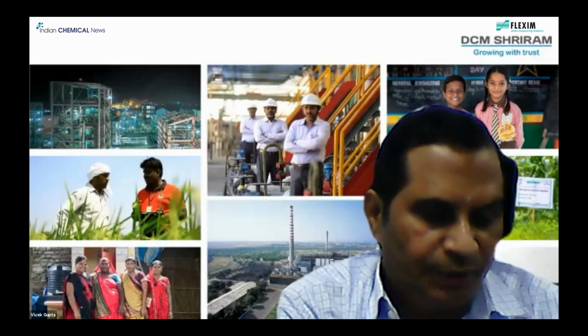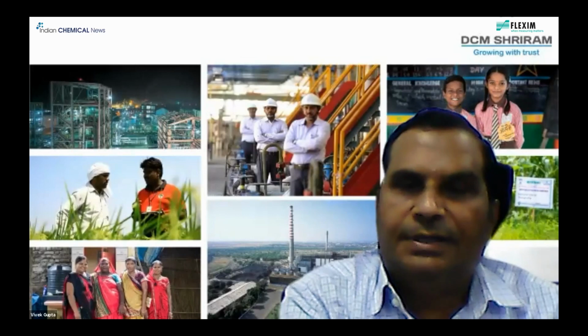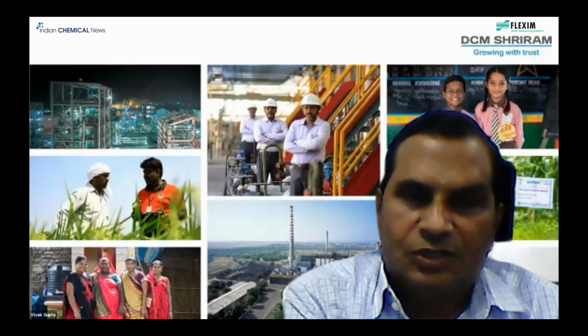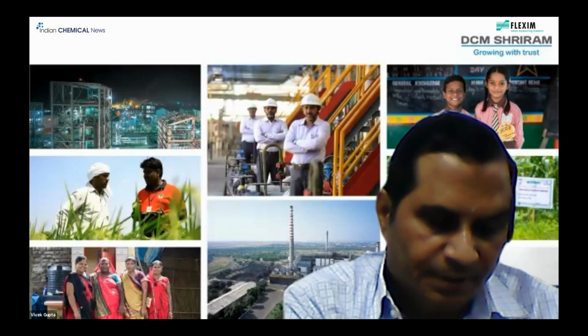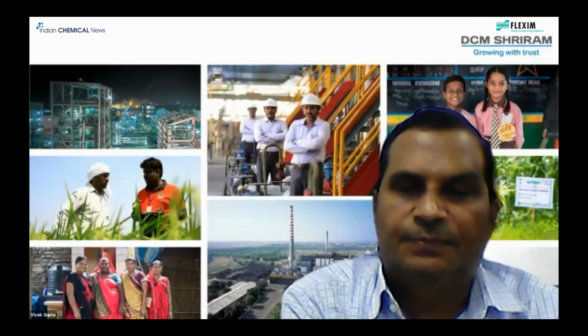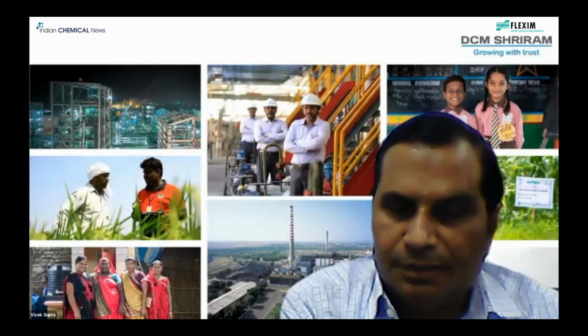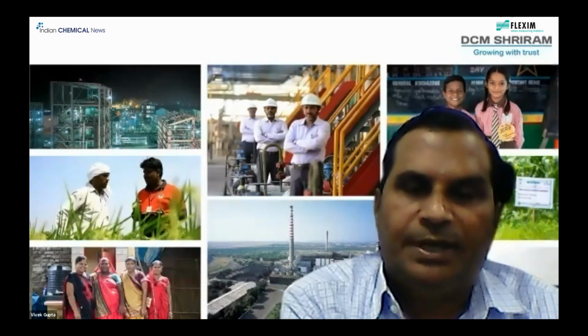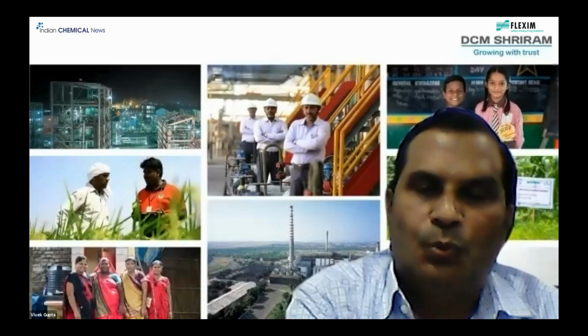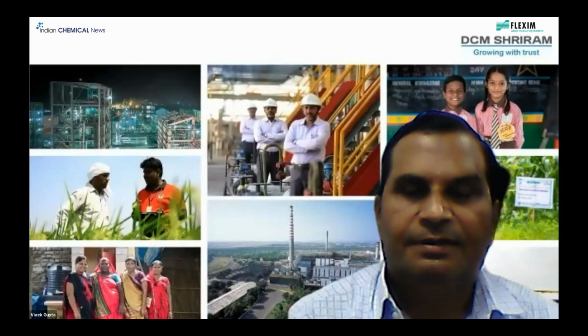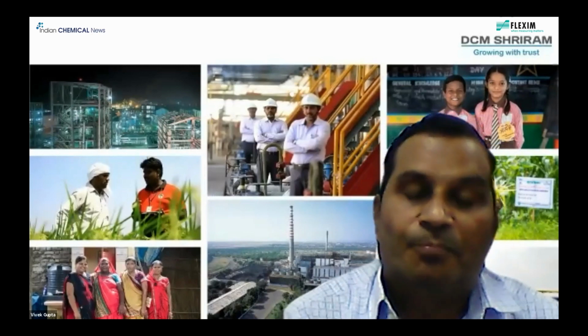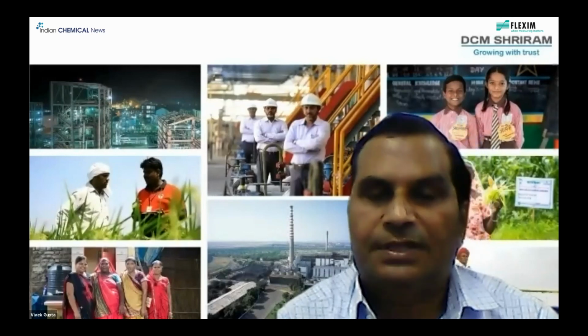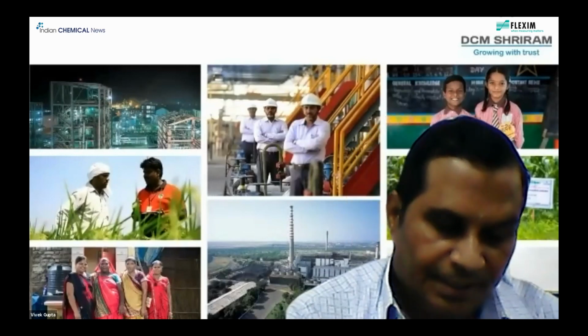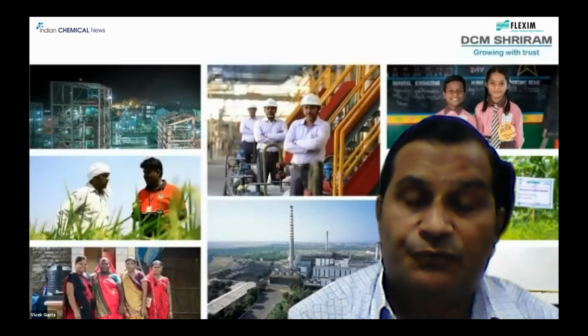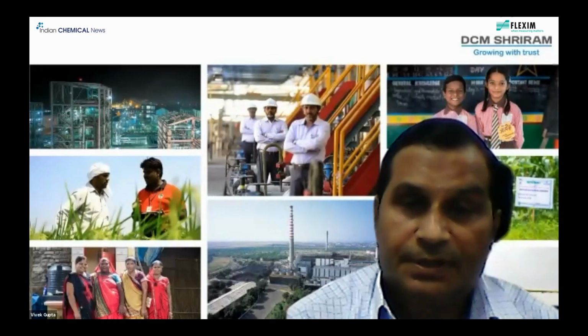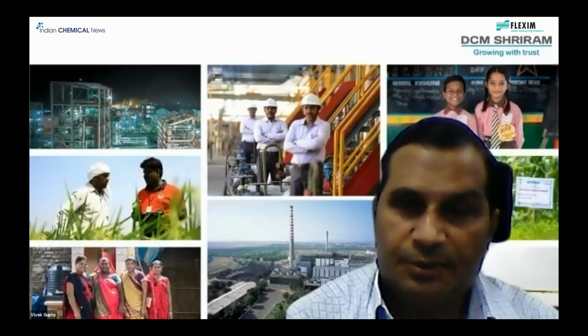I feel we are getting good results because it is a non-contact type, and the CS pipe is acoustically transmissive. The beauty of this system was that this was such a big line which is underground. With this clamp-on type, we get one advantage: we can put the sensors on one side of the pipe, which means it's not essential to have access to the pipe from both sides. So we installed the sensor on the one side where we have access. The flow range is also quite wonderful, up to 15,000 meter cube per hour of water. This is one application which is working perfectly fine at the power plant.